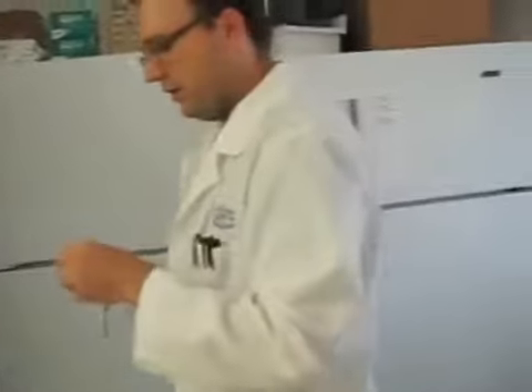And it should be noted, the standard 1 millimolar needs to be kept refrigerated and also away from light, because the concentration will change over time. So that's important, especially with your calibration. You want to make sure you have accurate data.